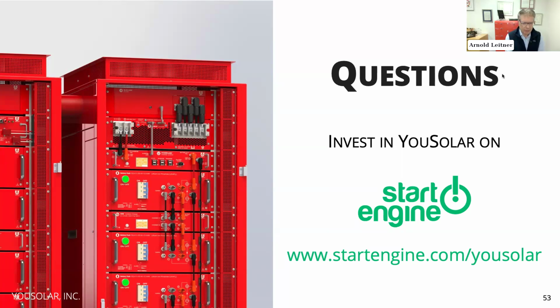What about cooling the system? Yesterday we visited a site with about 8 or so Fronius inverters running a grid-tied system, giving off the same heat any inverter gives off. We're realistic with our customers - this is a very high power system, not a 5 kilowatt backup battery on the wall in the garage. This is a 50, 100, or 200 kilowatt system - it's an industrial piece of equipment. That's why we have these vent hoods, which you see on the left here on top.